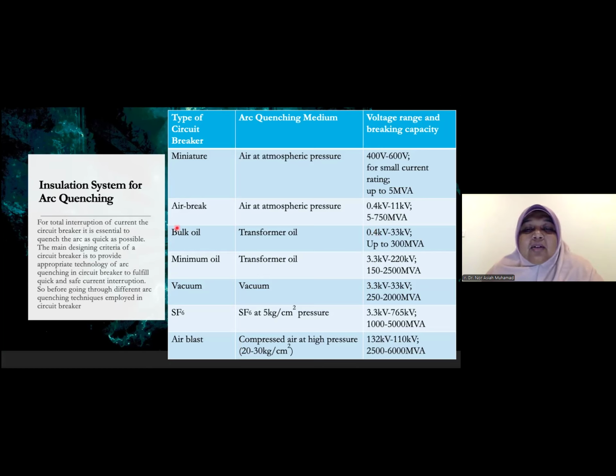So we have the bulk oil circuit breaker, where the arc quenching medium is transformer oil. We have the minimum oil circuit breaker, also using transformer oil. Then we have the vacuum circuit breaker, where the arc quenching medium is vacuum. We have SF6, at a certain pressure, because for gas, pressure is very important. For gas or air, the pressure is important because SF6 properties will not be the same when the pressure is not at the specific required level.